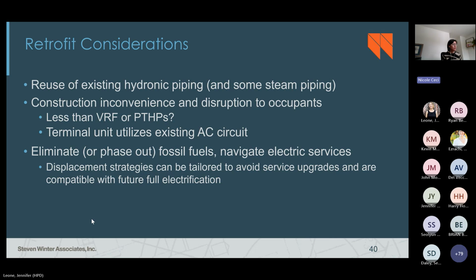We also often can reuse an existing air conditioning circuit for some of the terminal unit options that are available on the market today. And that can help us avoid expensive and invasive rewiring in apartments. And last bullet point here, I want to note that there is a displacement strategy modification available. There's an option on the table with this system, because again, it's flexible, it's water. So in that displacement option, you would size your air-to-water heat pump plant to be equivalent to roughly the size of the existing electrical service capacity that you have to work with in the retrofit. And that way you'd avoid doing an expensive electrical service upgrade. And then you would use fuel-fired boilers to meet the rest of the peaking load.